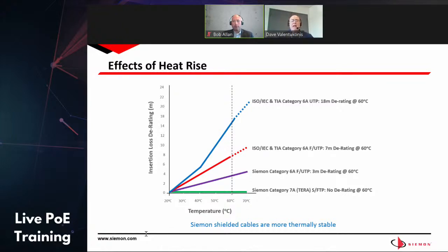Keep in mind, that worst case scenario may not be day one, when you're maybe only running a few PoE devices, type one or type two. But your infrastructure is designed to last 10, 15, 20 years, and by then there will likely be more devices running at higher PoE levels. So you want to start planning for this now, not when it becomes a problem.